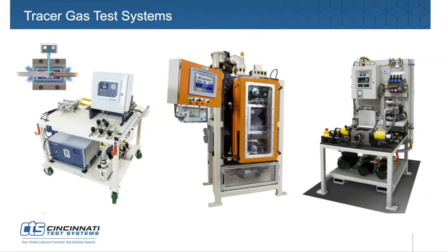And many of our customers test lower than that, and they need to use helium hard vacuum mass spec testing, which is evacuating all the gas around the part in the chamber, and then measuring helium leaking into this vacuum source with a mass spectrometer. And for those of you that say, why would you use a tracer gas?